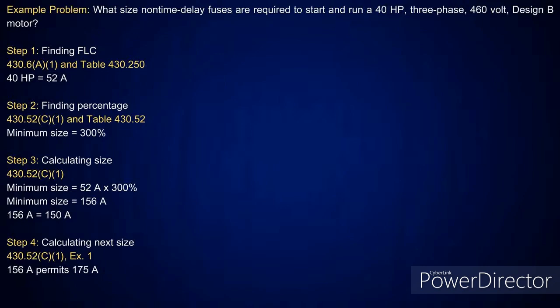I've had people ask me questions while we were live, and I just made up a problem. But I'll make one up different from this, and I think we even have it in one of the other slides. Let's say I have a motor, and I'm going to size an inverse time circuit breaker. We'll say it's a 50 horsepower, 460 volt, three-phase Design B squirrel cage motor. Now, when I'm going to size the overcurrent protection device, Table 240.4(G) is going to reference Article 430.